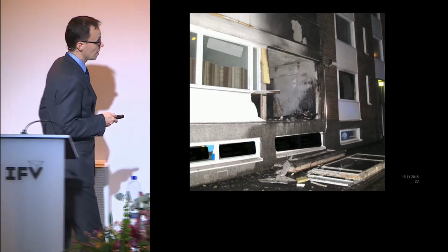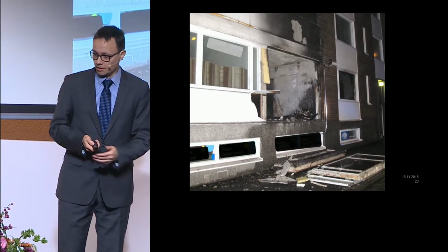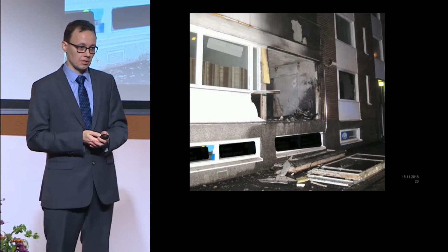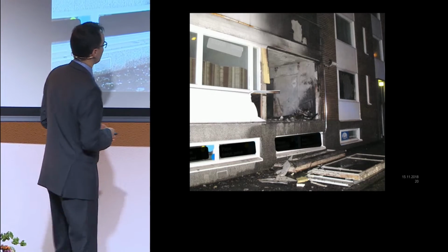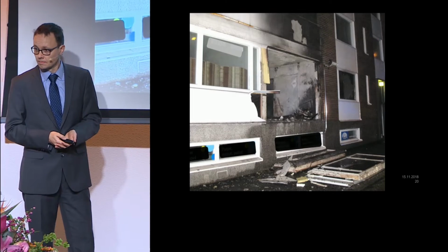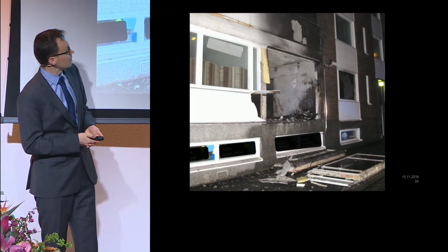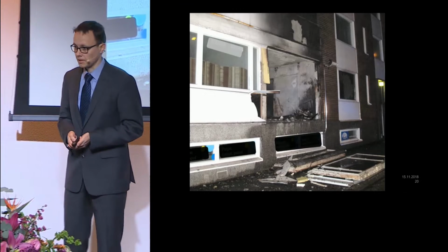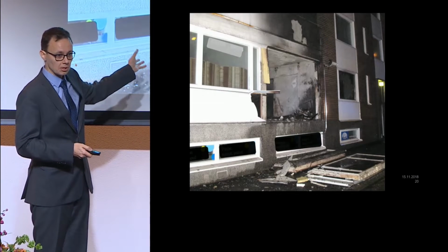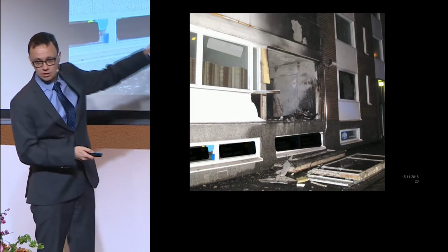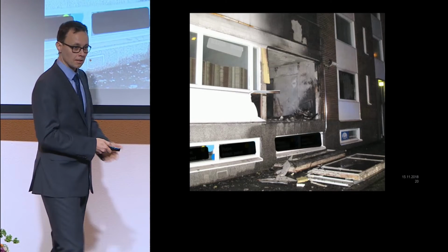Structures. I had this photo from the fire department of the city of Tampere. What we see is a small apartment on the first floor. We see that there has been a really heavy flashover fire consuming basically all the combustibles. We see plain, clean, nice concrete surfaces. Even the soot has been burned away.